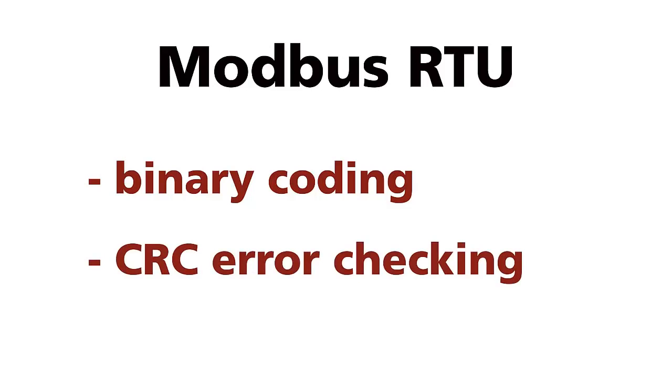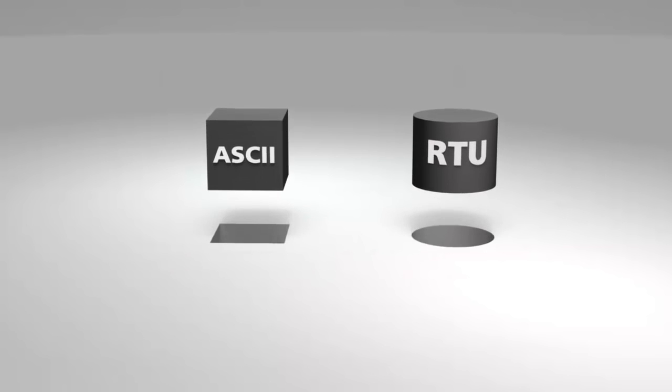Modbus RTU is by far the most common implementation using binary coding and CRC error checking. The two modes are incompatible, so a device configured for ASCII mode cannot communicate with one using RTU.